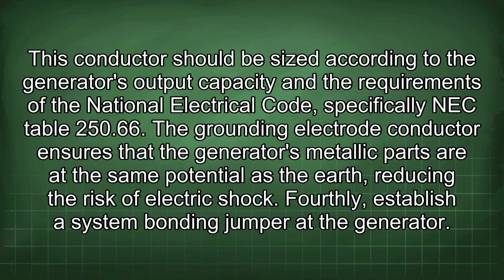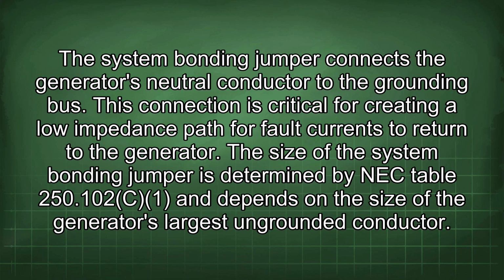Fourthly, establish a system bonding jumper at the generator. The system bonding jumper connects the generator's neutral conductor to the grounding bus. This connection is critical for creating a low impedance path for fault currents to return to the generator. The size of the system bonding jumper is determined by NEC Table 250.102 and depends on the size of the generator's largest ungrounded conductor.